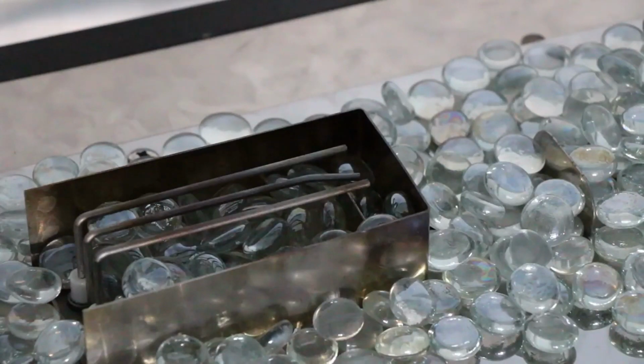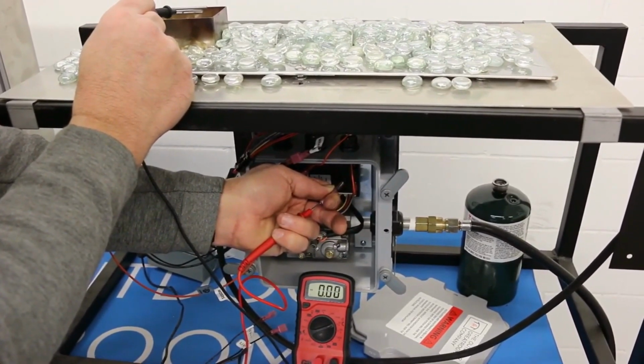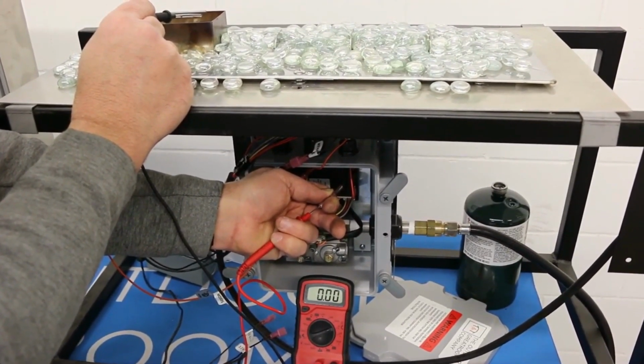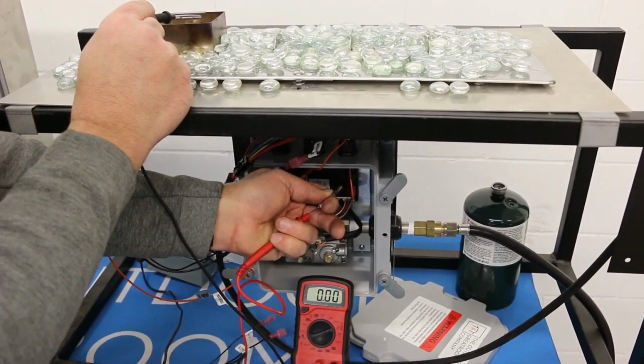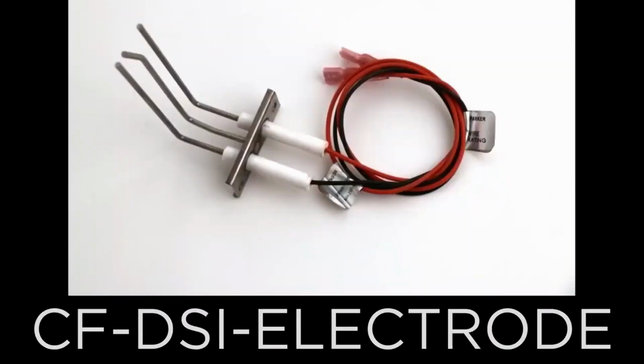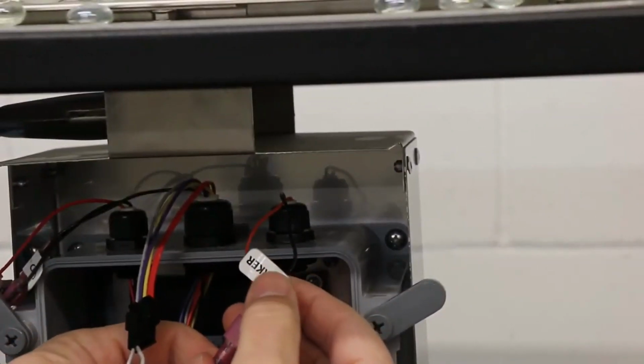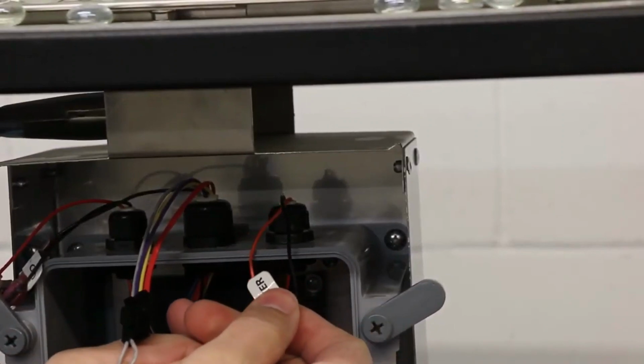If you hear a beep and the clicking of the sparker, but do not see it on your electrode, you can check the continuity of your sparker by disconnecting the sparker wire from the module and checking continuity from that lead to the actual igniter rod. If no continuity, you either have a bad wire or need a new electrode, part number CF-DSI-electrode.